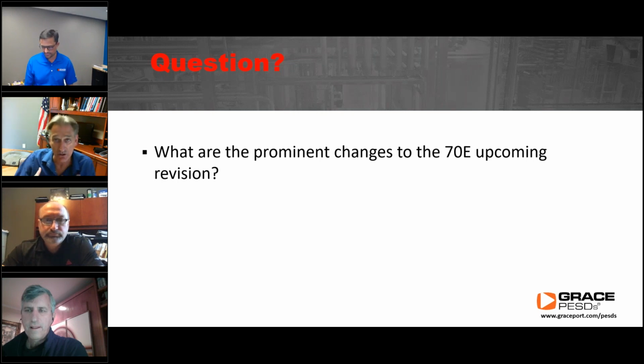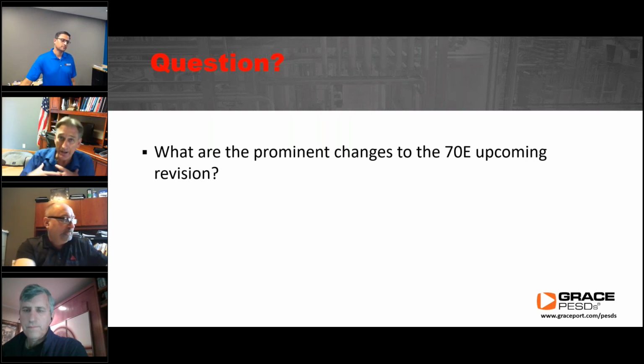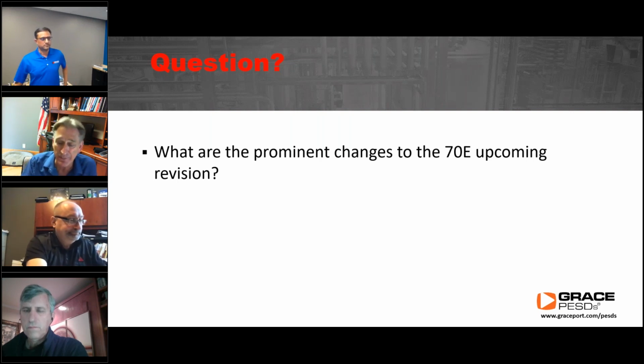Well, this is a change to me. I heard some of the other instructors saying, oh yeah, I've been teaching it this way all along. Well, I haven't. The note that's going to be added will say the arc rating of the outer layer worn over arc rated clothing as protection from the elements, or for other safety purposes, such as a high-vis vest, that is not used as part of the layered system shall not be required to be equal to or greater than the estimated incident energy exposure. This is also going to show up in table 130.5G and in table 130.7C15A or C15C for PPE, when it's talking about high vis clothing - the outerwear has to be arc rated, but does not have to be equal to or greater than the potential incident energy.